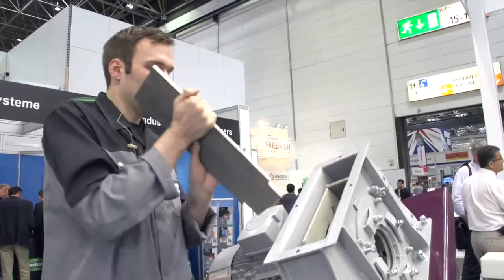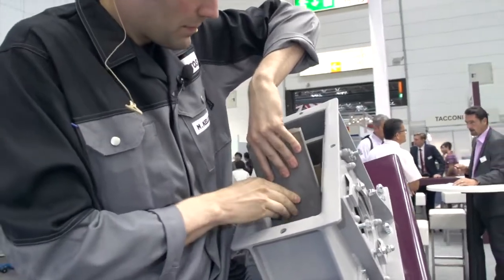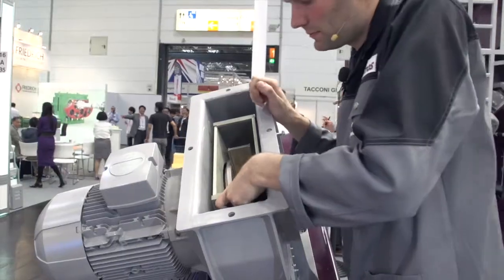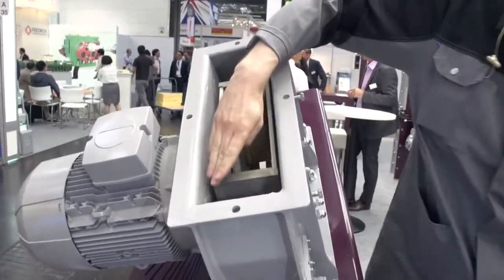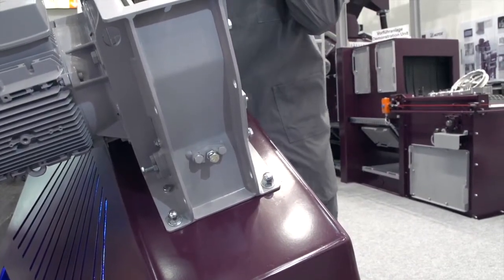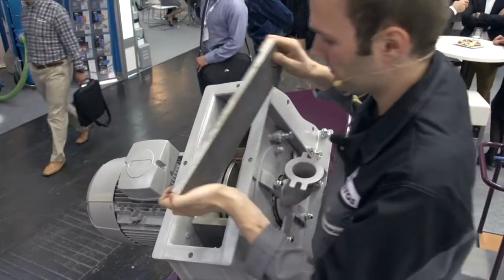In order to install the front plate of the wear-resistant lining, push it into the turbine housing until it reaches the stop. The position is correct if the front plate of the lining material has the same height as the lateral lining plates in the turbine housing. Then tighten the clamping screw and lock nut at the turbine housing.